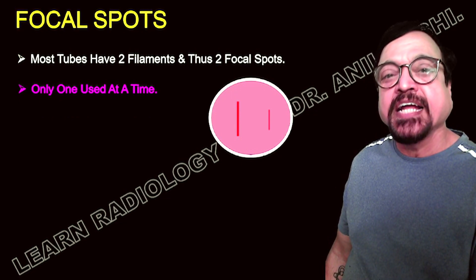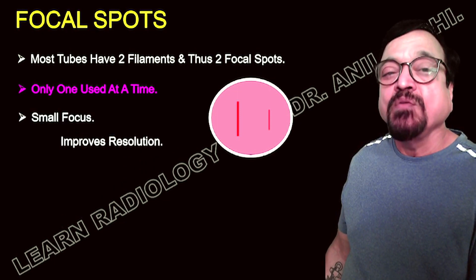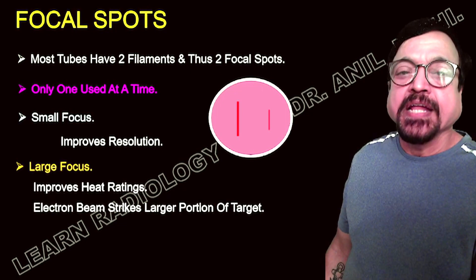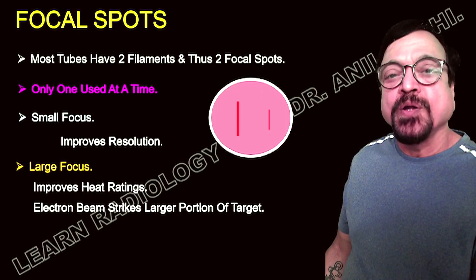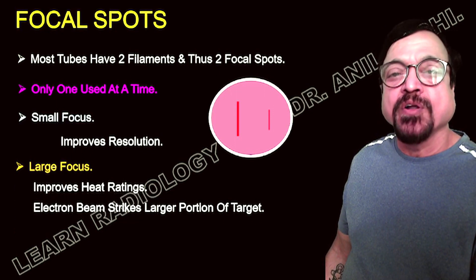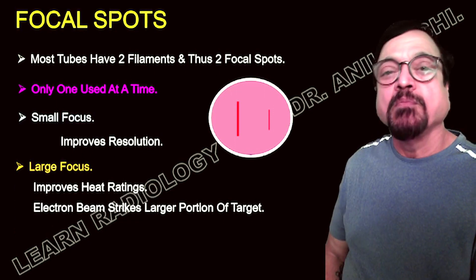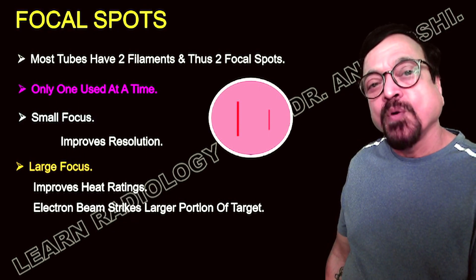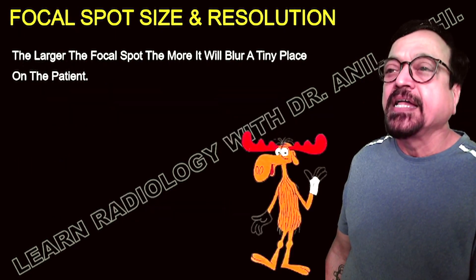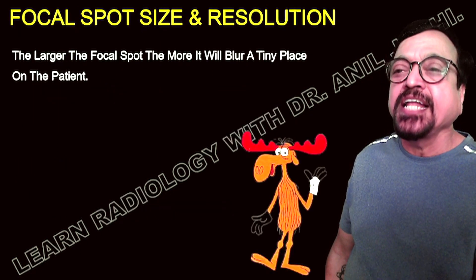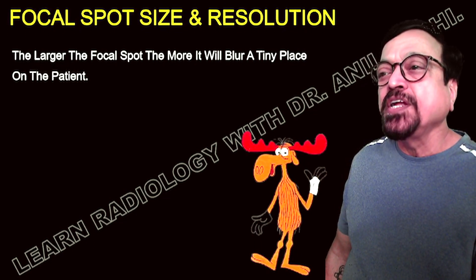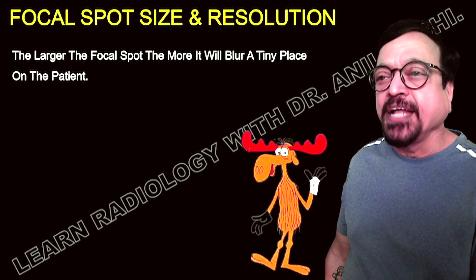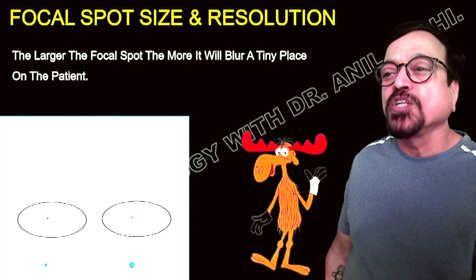A small focal spot gives a sharp image but cannot handle high mA. The large focal spot can handle high mA and longer exposures but gives a less sharp image. Only one focal spot is used at a time — either small or large, not both simultaneously. When you want good resolution you select the small focal spot, but you will need to use more seconds since more mA cannot be used. The large focal spot uses more mA and allows longer exposures but is less sharp.